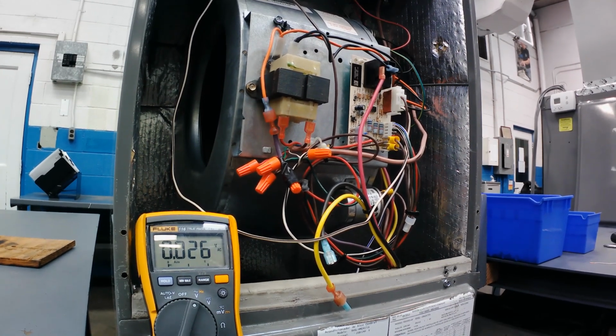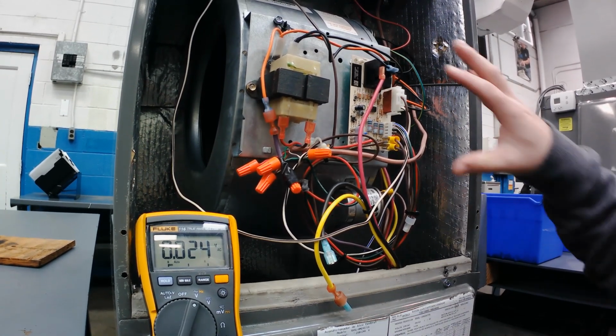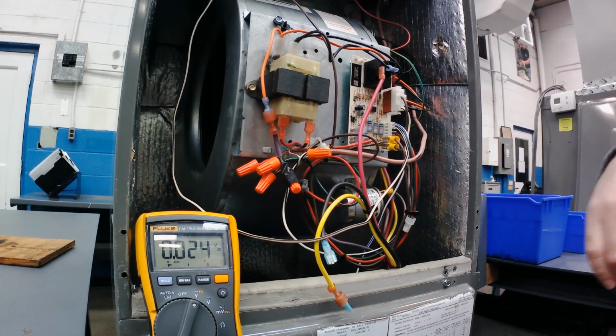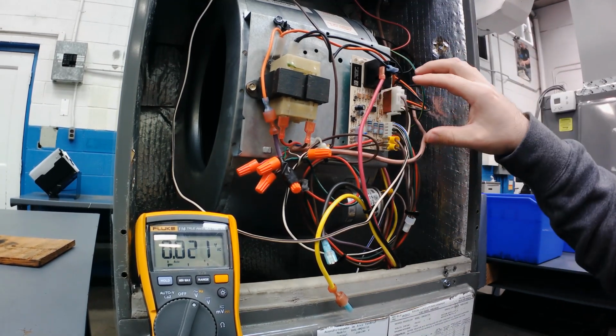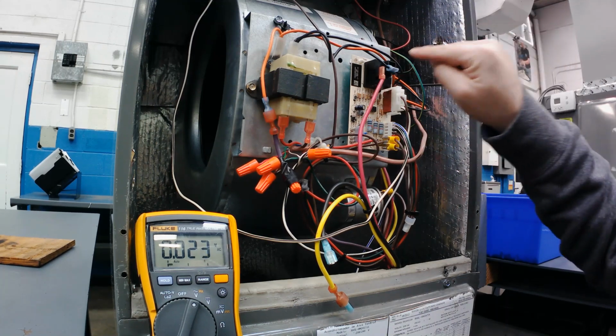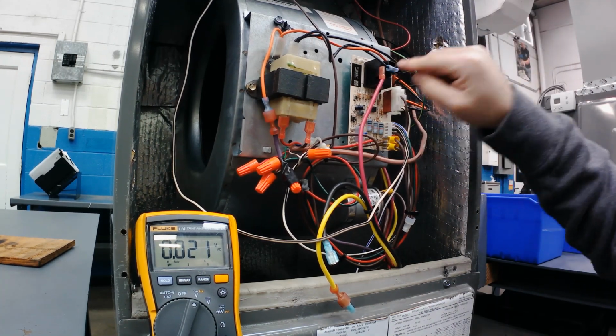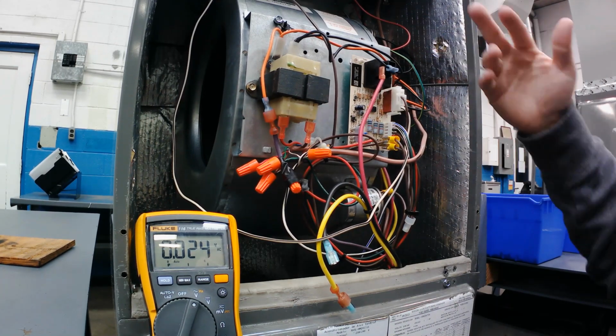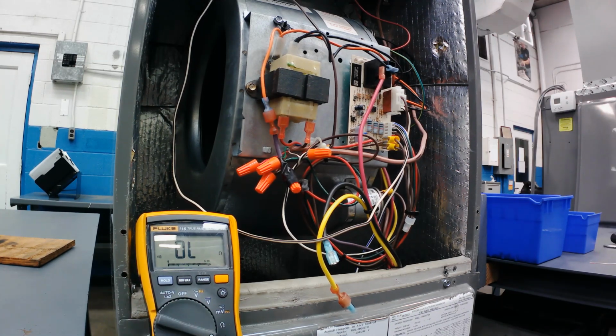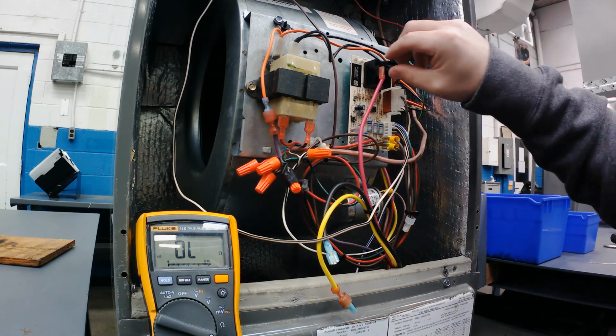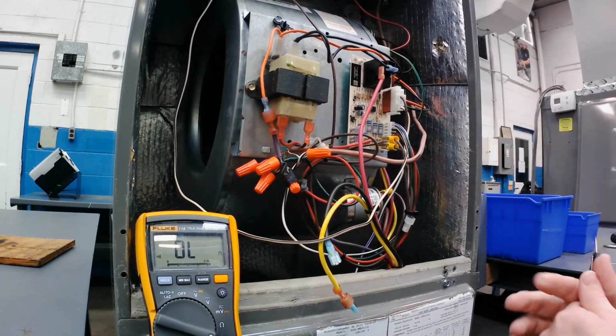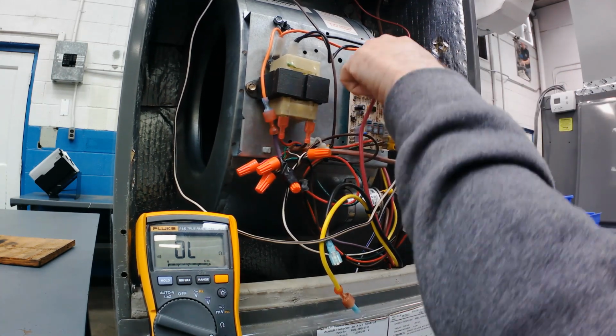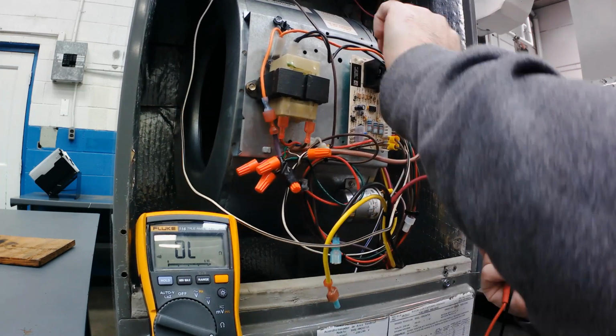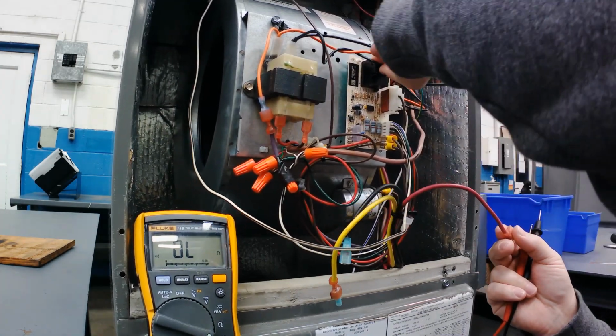A lot of young guys that I see think that when you pull one wire off, you have to pull them all off. I can leave all the low voltage connected to this board, and if I'm just troubleshooting that switch on that relay, then I can use continuity, and I'll set my meter to continuity, and I've got it with my leads. But if I wanted to check this switch, maybe it's a burnt up switch, there's some carbon or something in there, I could unplug this, right?